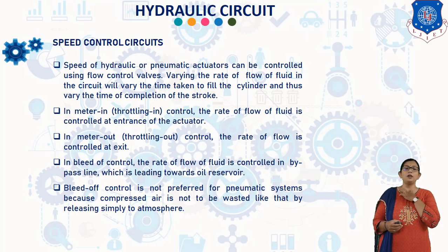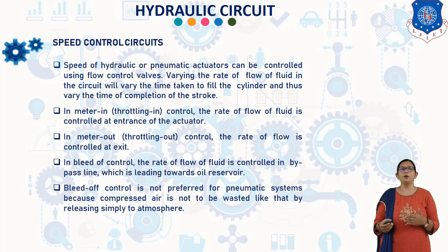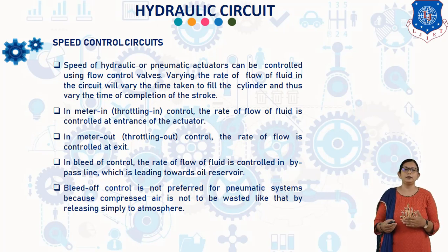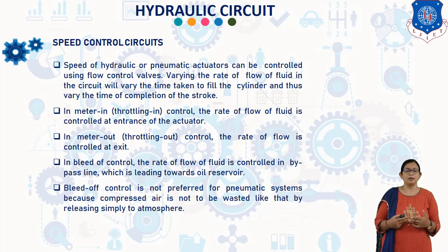Now we will discuss the speed control circuit. The speed of hydraulic actuators can be controlled using a flow control valve. Varying the rate of flow of fluid in the circuit will vary the time taken to fill the cylinder, and thus vary the time of completion of the stroke. Generally, there are three circuits used for speed control: the meter-in circuit, the meter-out circuit, and the bleed-off control.